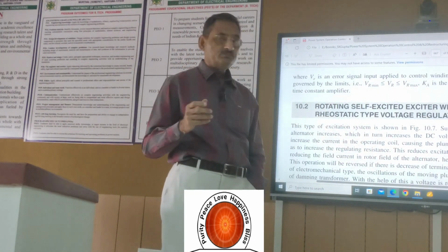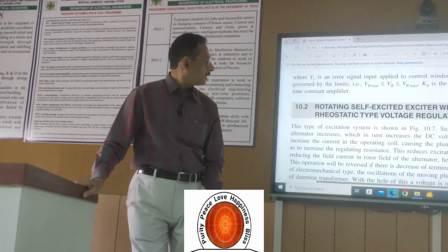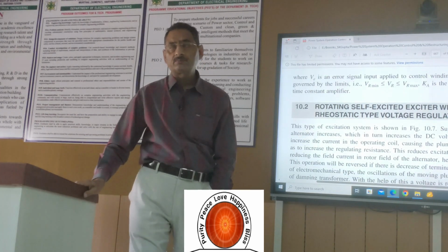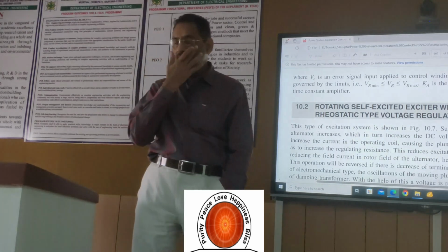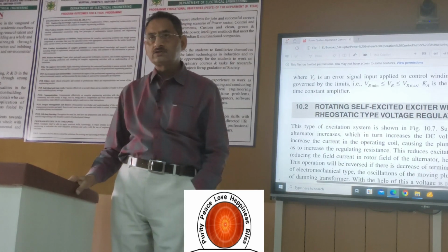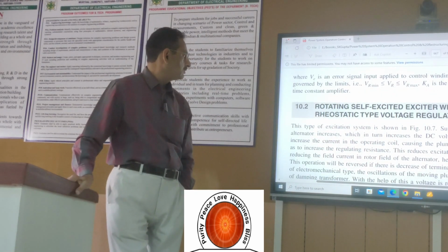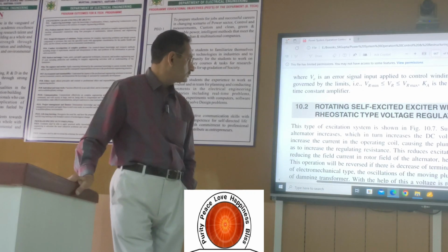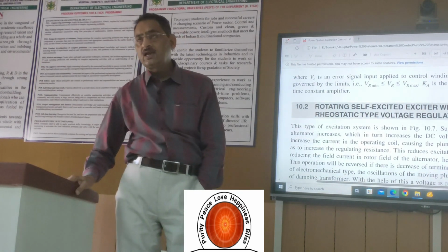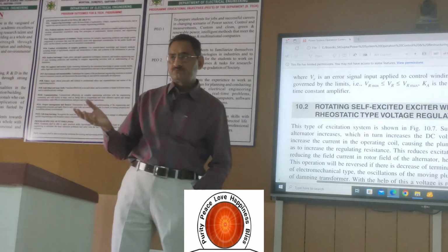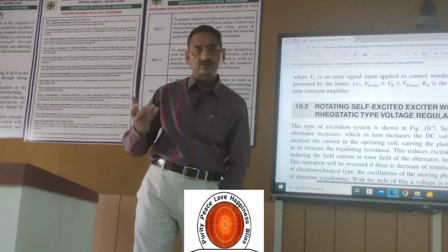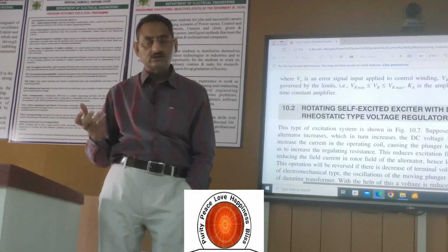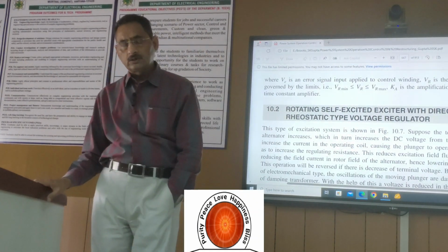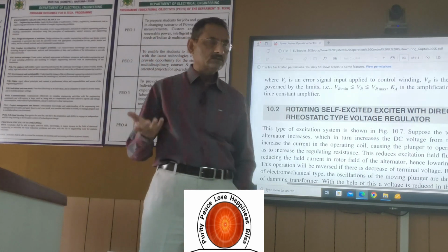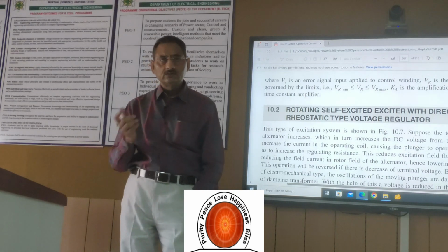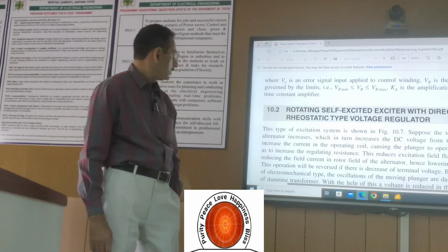So along with the basic theory, we described one type of excitation system. I told there are DC excitation systems and AC excitation systems. Out of the DC excitation systems, we described this one: rotating self-excited exciter with direct acting rheostat type voltage regulator. Means it is a self-excited exciter, though an exciter can also be separately excited. What is an exciter? In this case, a DC generator supplies the DC current to the field of the synchronous generator. So it is a DC generator, and a DC generator can be either self-excited or separately excited. In this case, it is a self-excited exciter and directly acting rheostat.